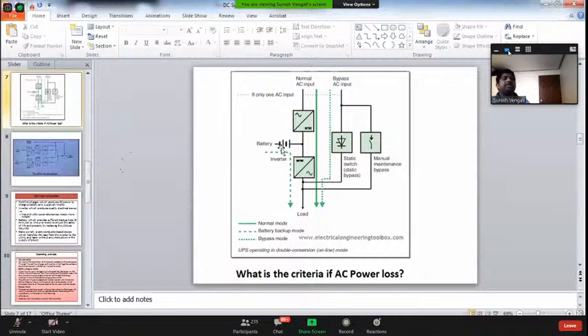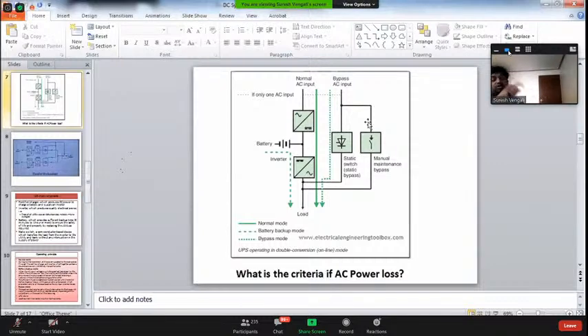So through that only you can control the UPS. But individually there is no box for the UPS. Again, you have a control feature: this battery breaker is wired to your control room. If you wire to that particular location, hardwire, then you can control it. But there is no soft approach, no Modbus or anything - they don't allow that because these are very critical loads. Critical loads generally don't use soft signals, only hardwire signals. So if you want to control like that, you can wire up to any control room and control it. You can change all modes also through that.